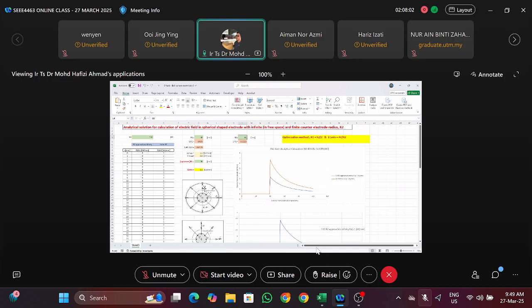Their electric strength is better. Solid is 100 kV per millimeter, so it is very strong, and liquid is 30 kV per millimeter. According to this electric field, you can see the maximum here is 6.6 kV per millimeter. Then I can use SF6, because SF6 will break down at 9 kV per millimeter, or I can use oil at around 30 kV per millimeter. So that is the design. Or I make it bigger, maybe 100 millimeter, and this is 50 millimeter.